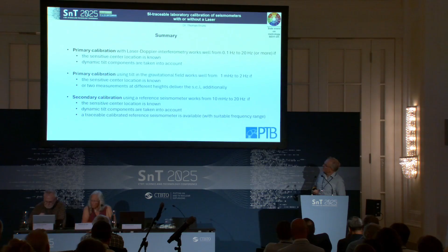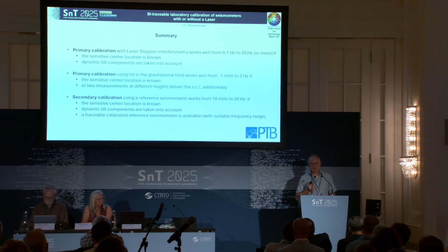And secondary calibration using a reference seismometer works well from 10 millihertz to 20 hertz if, again, the sensitive center location is known, dynamic tilt components are taken into account, and a traceable calibrated reference seismometer is available in the suitable frequency range. Thank you. Thank you very much, Thomas.